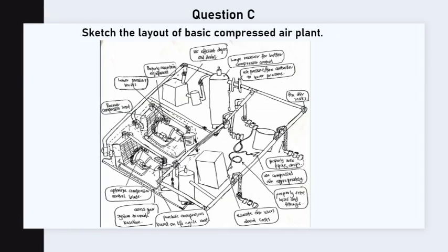As we can see in this sketch, on the left side: use a compressor or flow controller to lower pressure, large receiver for better compressor control, use efficient dryers and drains, properly maintain equipment, lower pressure level, recover compressor heat, optimize compressor control, assess your system to create a baseline, and purchase compressors based on life cycle costs.